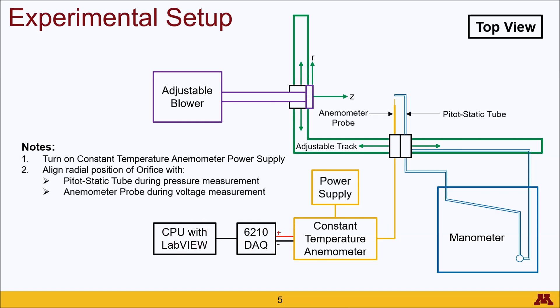Some notes about this: you need to turn on the constant temperature anemometer power supply, and you want to make sure to align the orifice from the adjustable blower into two different positions — one in front of the pitot-static tube and then the other in front of the anemometer probe. This will happen during the calibration process, so make sure you go back and forth between the two.